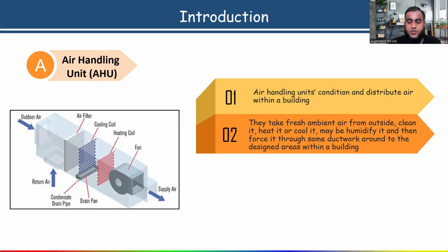Because all of you know what a humidifier is. A humidifier adds moisture to the air, right? In an HVAC system, in an air handling unit, generally we use a humidifier to add moisture, correct? And next, suppose for some location you are designing where the humidity level is more than 50%. Many cities are like that, where the humidity level is more than 70%, 80%. At that time, generally we have to install a dehumidifier. Because a dehumidifier is a mechanical device which removes excess moisture, meaning excess water content, from the air in the AHU. So this is the main purpose. Always remember, we have to maintain a 50% humidity level for human comfort. So the main purpose, I think all of you understood.